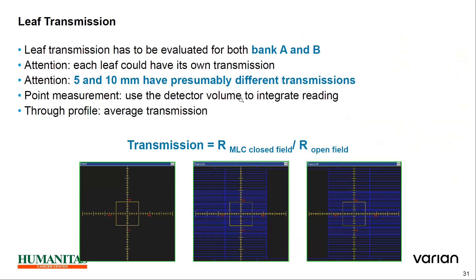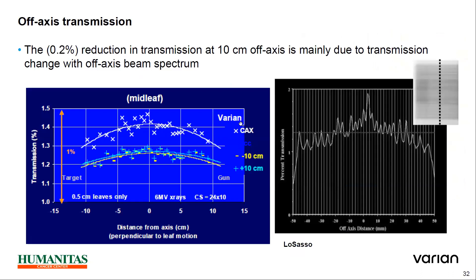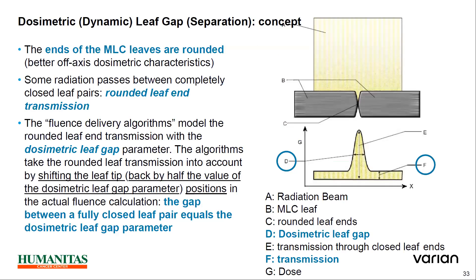For point measurement, use a detector with sufficient volume to average out the reading for transmission. The end of the MLC leaf is rounded, so better off-axis dosimetric characteristics. Some radiation passes between completely closed rounded leaves at the entrance. The fluence delivery algorithm models the round leaf end transmission with a dosimetric leaf gap.